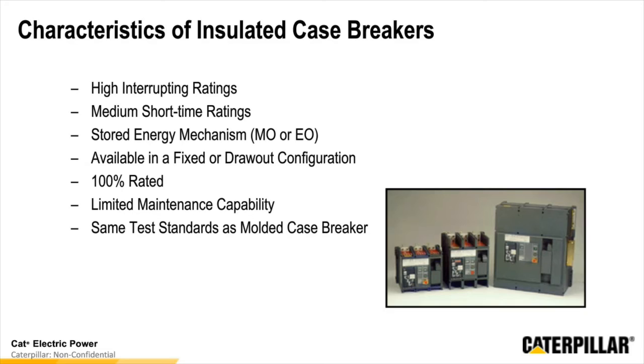They're available in a fixed or a draw-out configuration. They are typically 100% rated, and they have limited maintenance capability. So there's a few things that you're going to be able to change, but not necessarily everything. And they also use the same testing standards that you're going to find with those molded case breakers that we talked about.